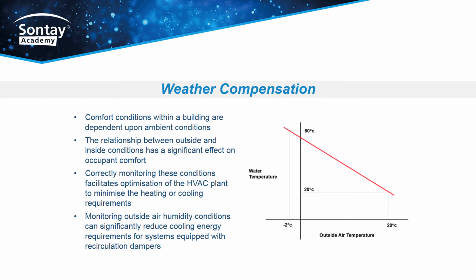There are many weather compensation strategies deployed within HVAC schemes. A very common method of conserving energy is to reduce the temperature of the water being delivered to the radiator circuit as the outside air temperature increases. Outside conditions also play a vital role in saving energy on systems equipped with mixing dampers. Sensing dry bulb temperature and relative humidity both internally and externally will allow the engineer to calculate the combined sensible and latent heat content, enthalpy, of the air at each part of the process.